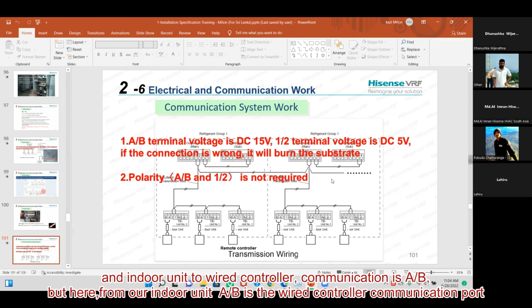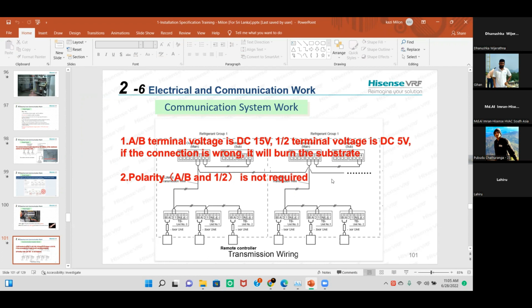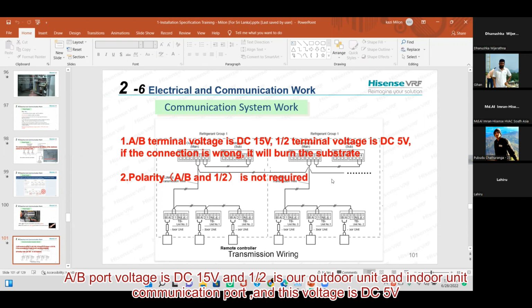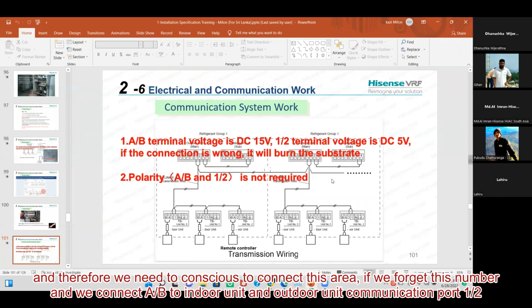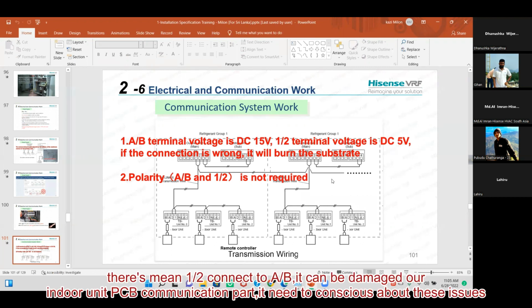From our indoor unit, AB is the wire controller communication port. The AB port provides DC 15 volt, and 1 2 is our indoor to outdoor unit communication port, which has DC 5 volt. Therefore we need to be conscious when connecting this area. If we forget this and connect indoor to outdoor communication, meaning 1 2, into AB, then it can damage our indoor unit PCB communication part. So we need to be conscious about these issues.